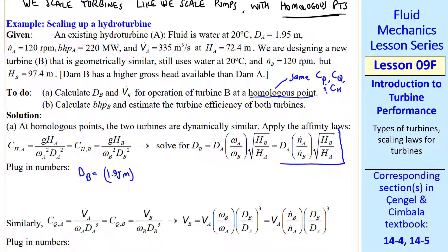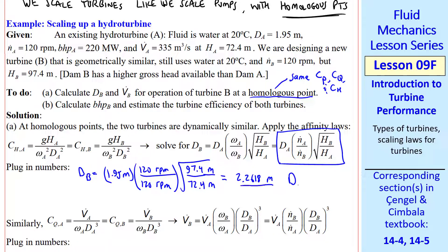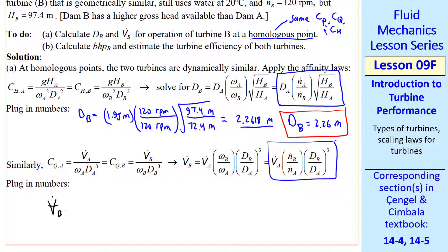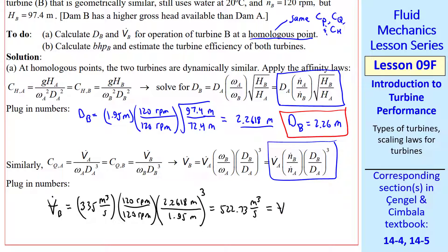Similarly, equating the capacity coefficients CQA = CQB, we solve for V̇B = V̇A × (ṅB/ṅA) × (DB/DA)³, and get V̇B = 523 m³/s. This is significantly higher than V̇A, so in times of drought you would be draining this dam quickly.